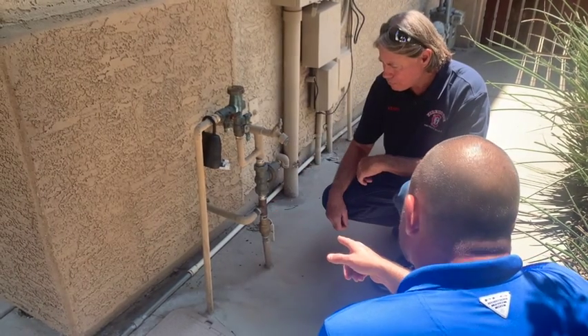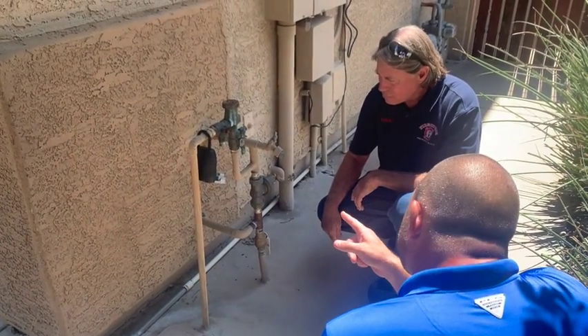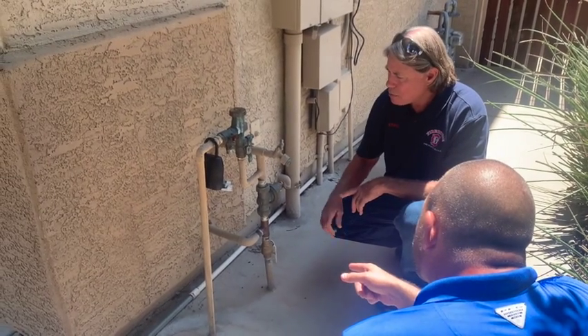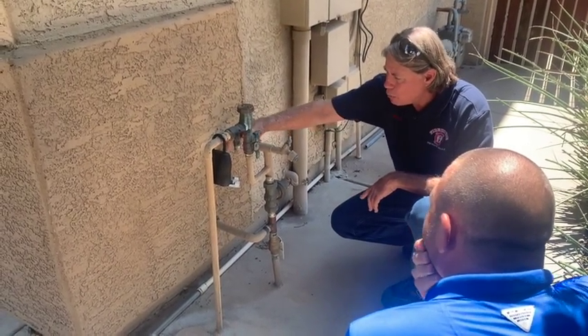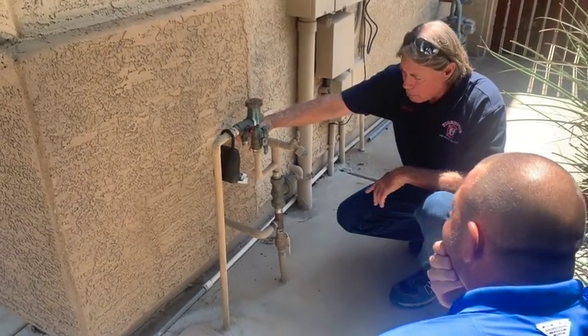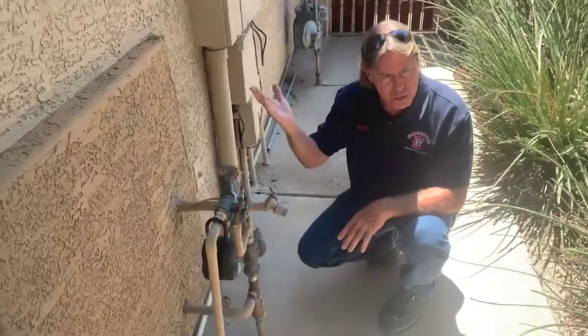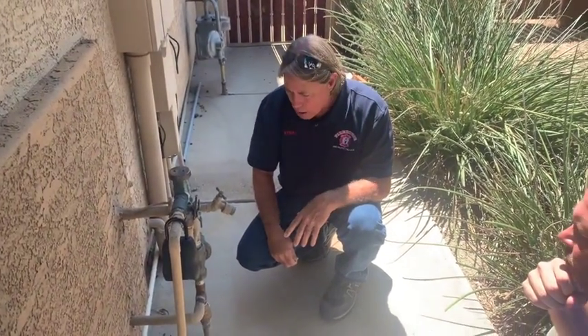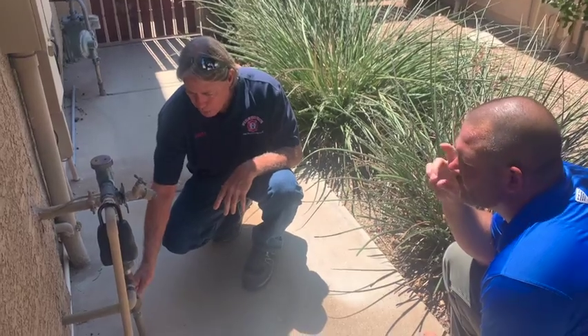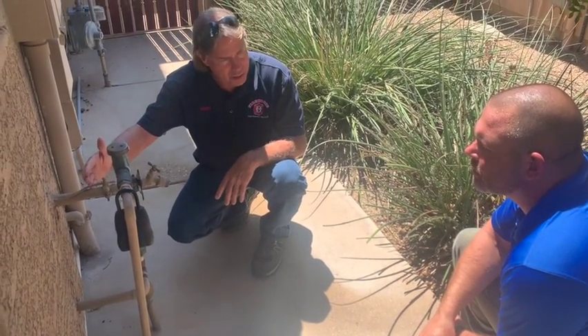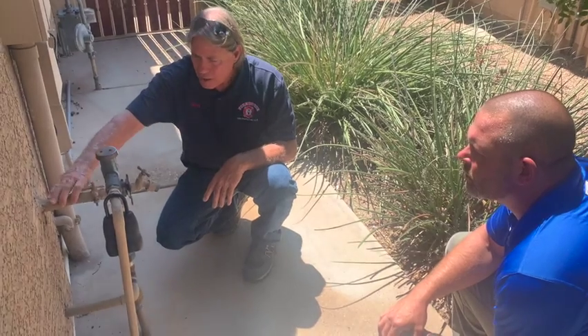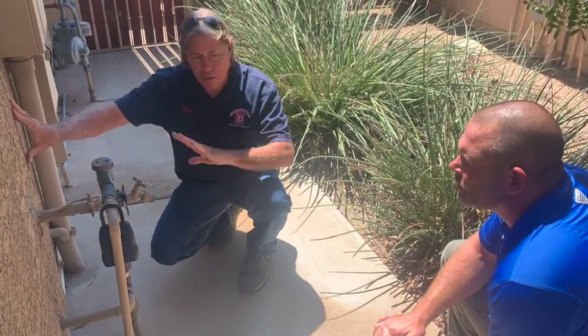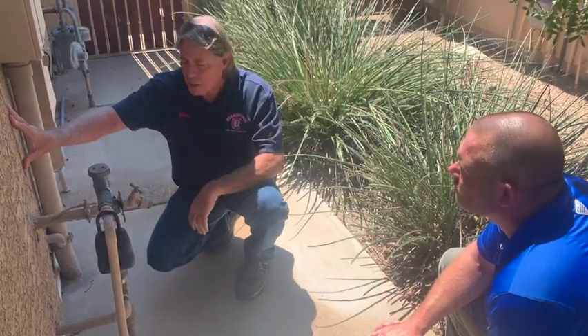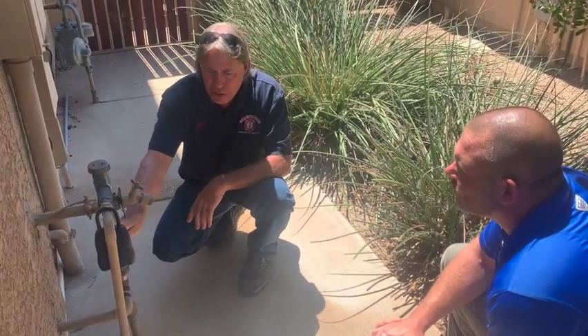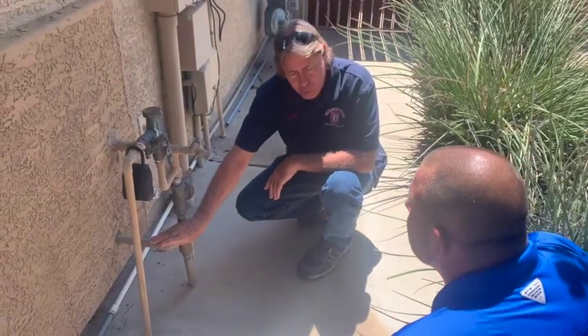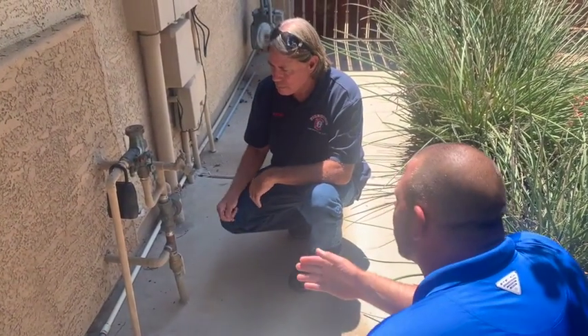Excellent. Okay. Now, on systems, should we have a secondary shutoff valve? A lot of times people have what we call a vacation valve, and that would be best located right here. And by current Scottsdale code, when we put in a new system, which we install new systems as well, they put it this way. We want a shut off before the PRV and a shut off after the PRV. The ideal place is here so that you can shut off your domestic water if you were to leave town, like on vacation or something. And that way you still have your plants and your irrigation will stay alive, and your fire sprinklers will protect your home. So not required, but recommended.